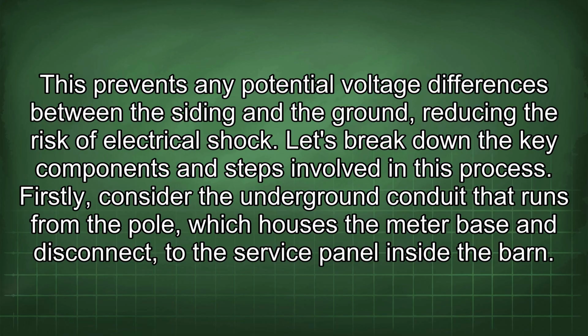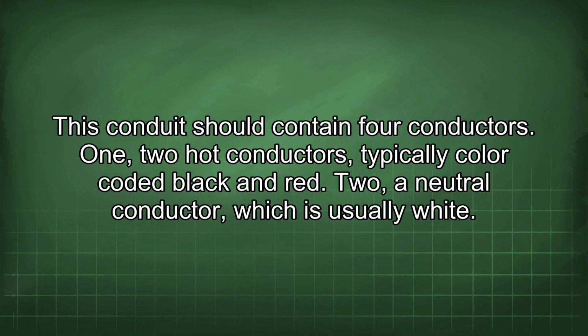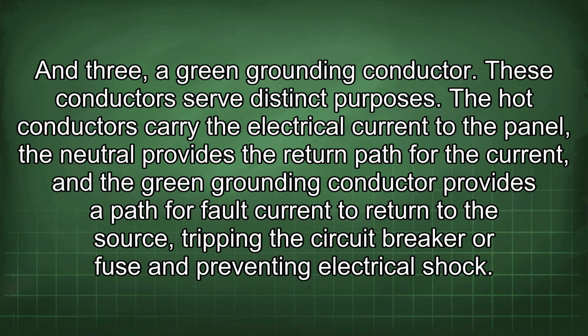Firstly, consider the underground conduit that runs from the pole, which houses the meter base and disconnects, to the service panel inside the barn. This conduit should contain 4 conductors. 1, 2 hot conductors, typically color-coded black and red. 2, a neutral conductor, which is usually white. And 3, a green grounding conductor. These conductors serve distinct purposes. The hot conductors carry the electrical current to the panel, the neutral provides the return path for the current, and the green grounding conductor provides a path for fault current to return to the source, tripping the circuit breaker or fuse and preventing electrical shock.